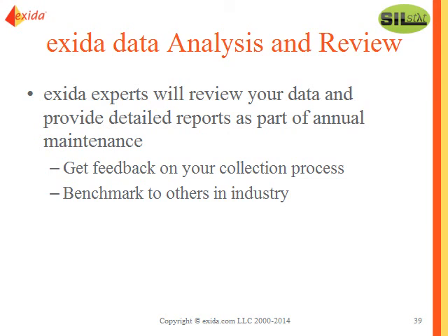Maybe weeding out some data that may not be applicable. Maybe you have systematic issues in there that shouldn't be accounted for in the random failure rate for a product. Maybe there are certain failures that are related to the product. Maybe certain failures are related to the maintenance process. We'll give you that feedback, and we'll benchmark that to others in the industry. So there's the data analysis and review, and that's part of your annual maintenance contract.